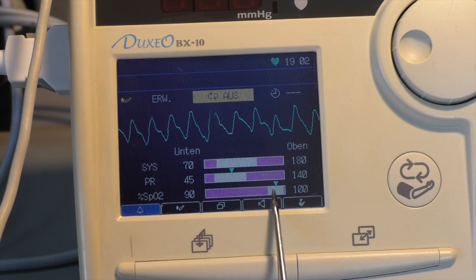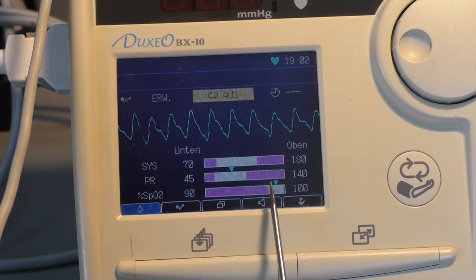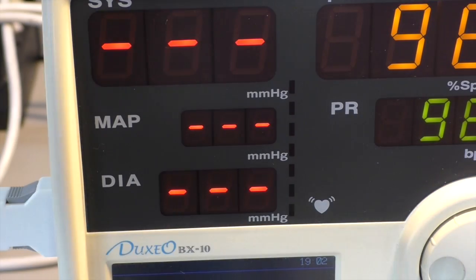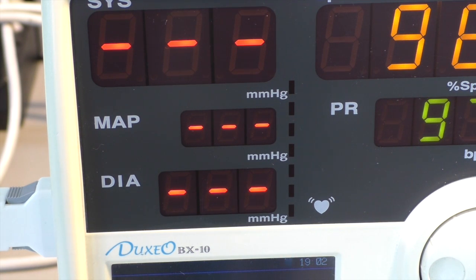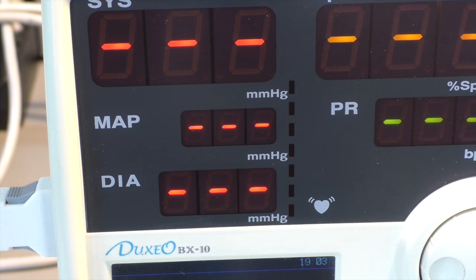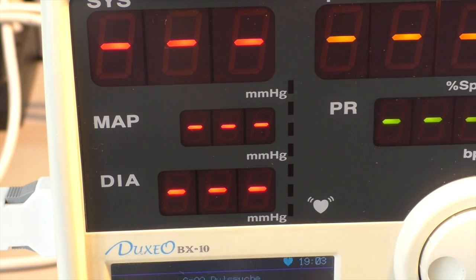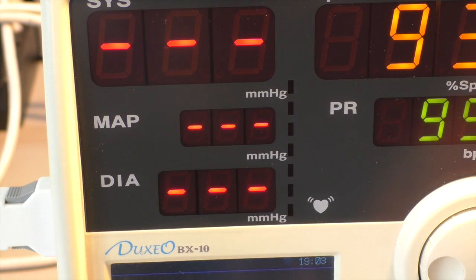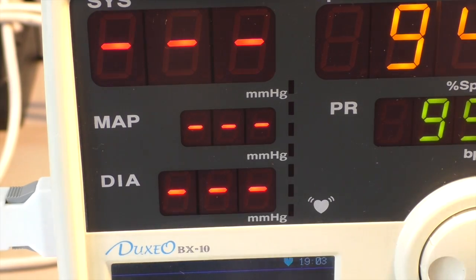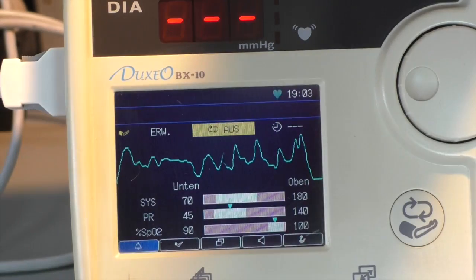The oxygen saturation alarm level is 90%, so if I go below that value, an alarm will sound. Maybe I can trigger that by opening this clamp. I'm not sure. I can't take my finger completely out because that would, well, that's what happens now. It cannot measure anymore. That gives a yellow alert, and if we go below the alert level here, we get a red alert, which tells the nurse that something bad is happening.